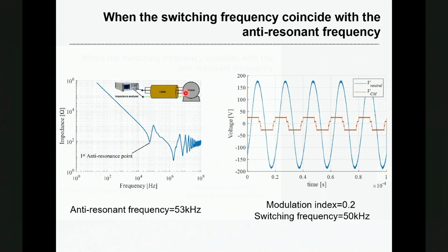But please pay attention to the anti-resonant point of the motor common mode impedance. Again, there is the anti-resonant point. And if your switching frequency coincides with this anti-resonant frequency of the common mode impedance of the machine, then you will have a huge overvoltage at the motor stator neutral. In this case, the frequency is 53 kilohertz.